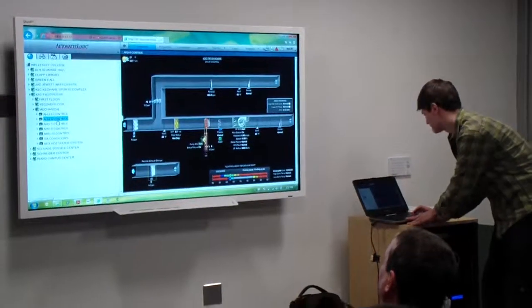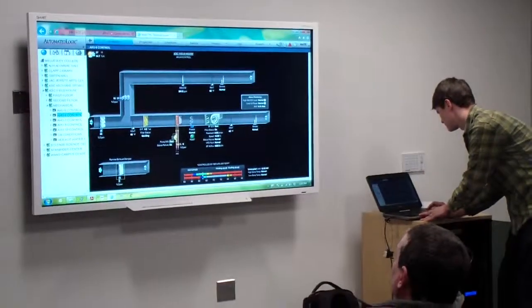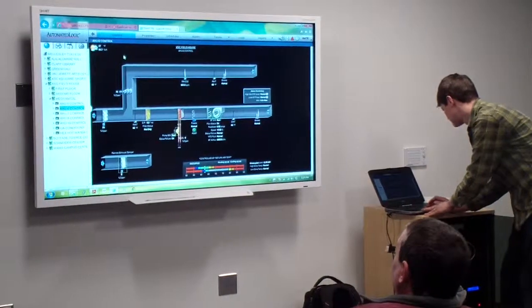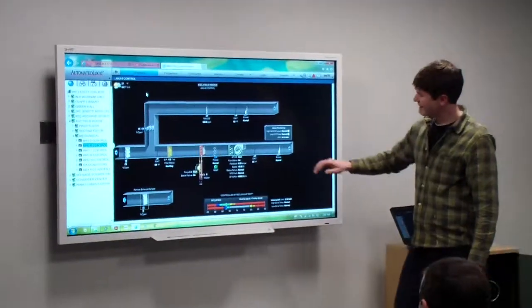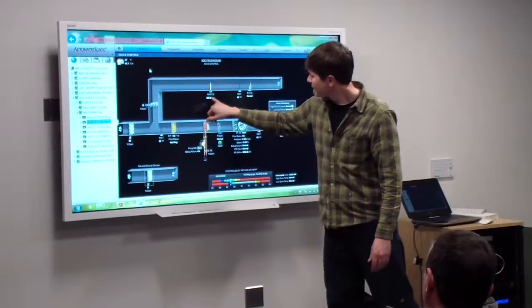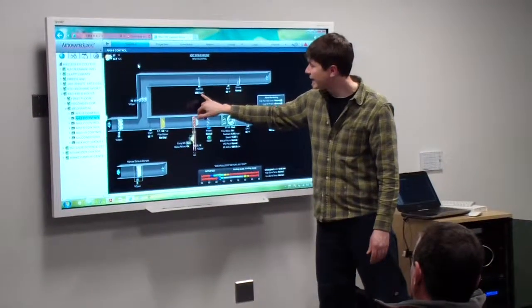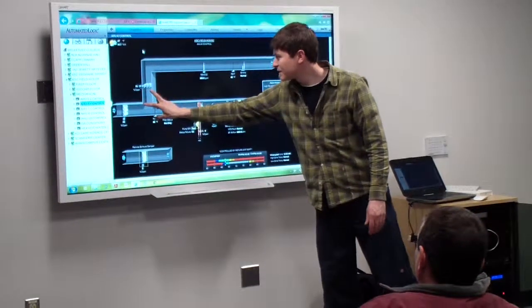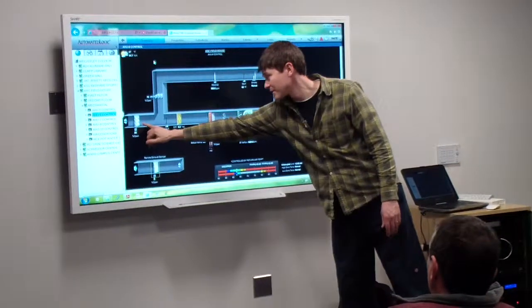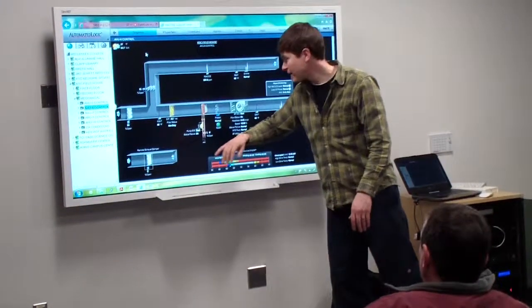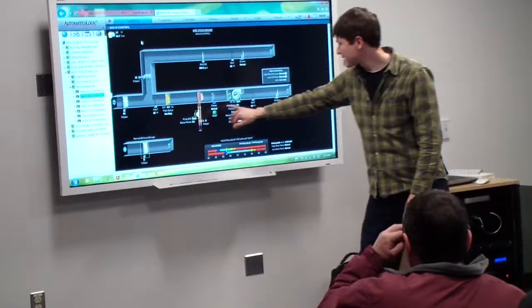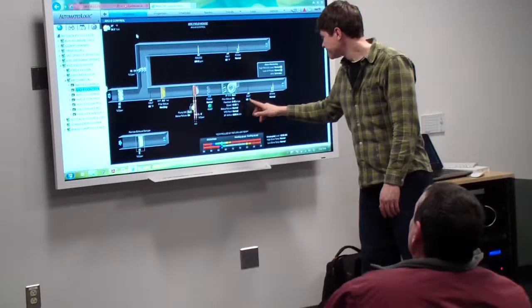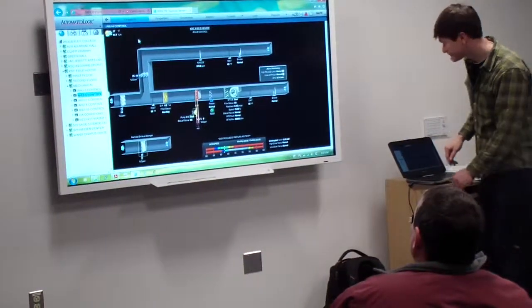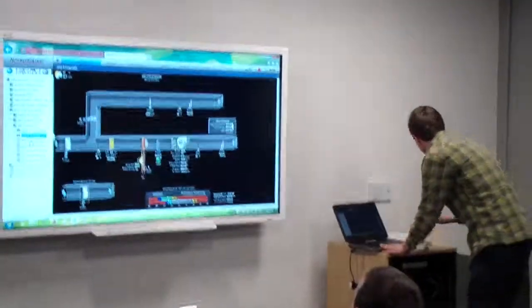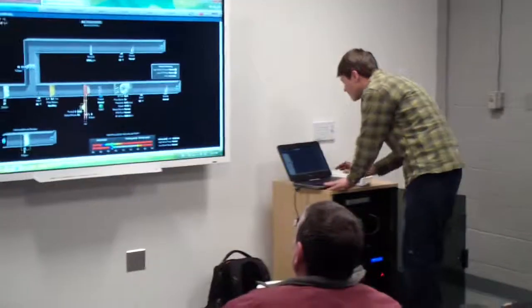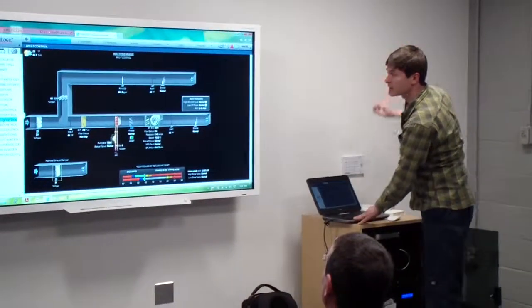Air handler 6. You see it's roughly doing the same thing. It's a little bit warmer over there, 63 degrees. Your CO2, 385, 75, 25, which these work inversely to each other. So as this closes, this one opens to try to keep a consistent amount of air. Same thing, our mixed air temp 56, the hot water valve circulating, 60-degree discharge temp. And that would take care of the 2 on this side, 5 being closer, 6 being further away, 7 being our closer unit on the left side.